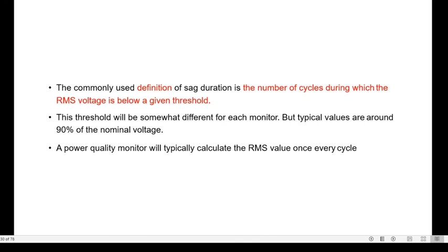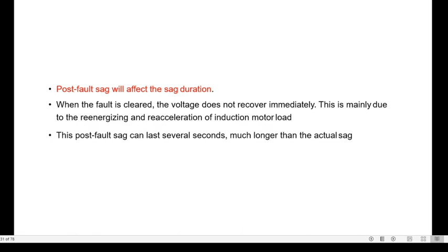Again, continuing with the same thread, the post fault sag will also affect the sag duration. After the fault is cleared, the voltage doesn't recover immediately. This is mainly due to the re-energizing and re-acceleration of the induction motor load, and others also. This post fault sag can last several seconds, much longer than the actual sag. That depends on the ability of the system to clear the fault.